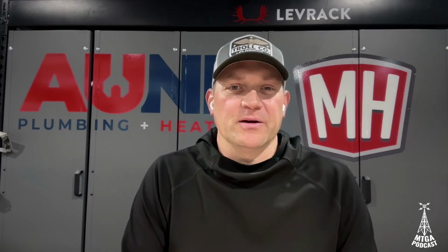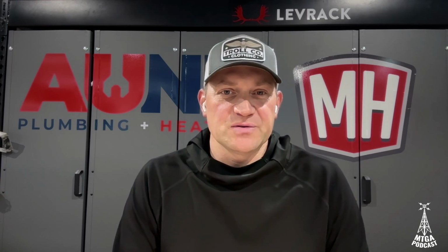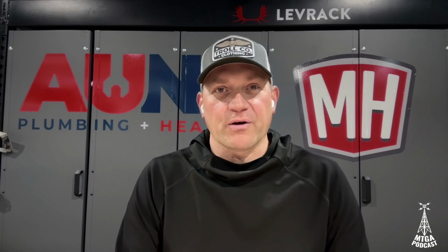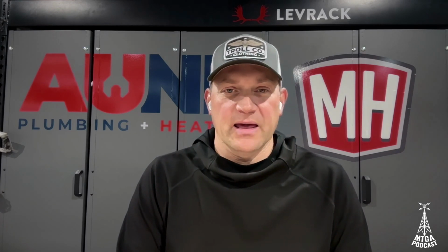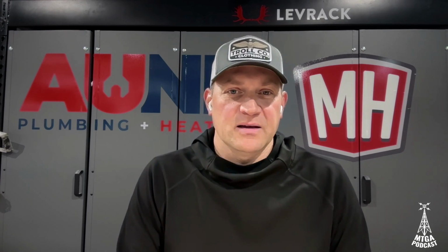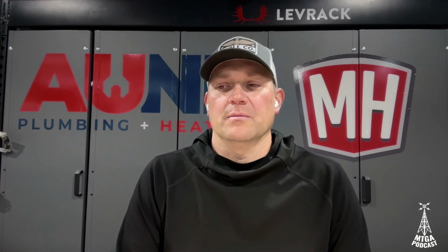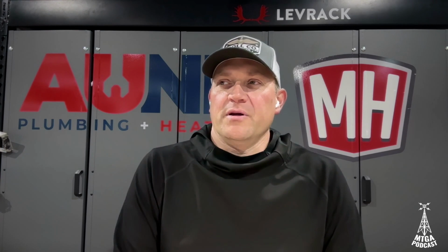So it's a monoblock system, which, if you've got any experience with that, sometimes throws up some pump sizing issues, as far as how far can you go? Do you have to worry about line set length and things like that from some of their other competitors? With the monoblock, you eliminate a lot of that. So that was nice, not having to worry about any refrigerant. This one used R32, low GWP, contained right out of the package, all in the outdoor unit. So, pretty cool system.